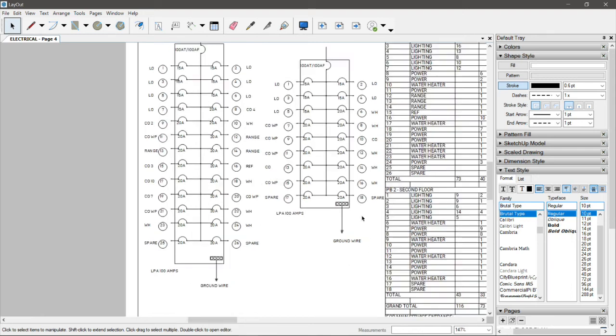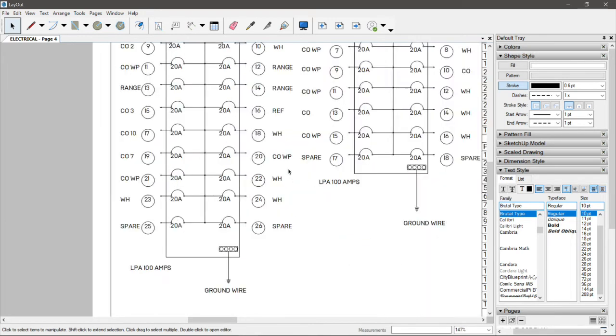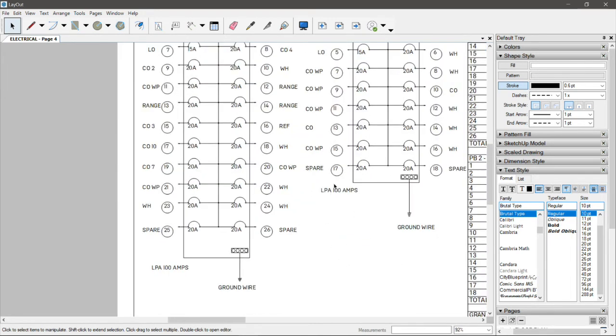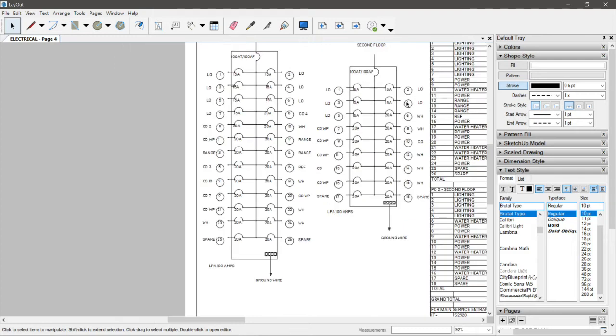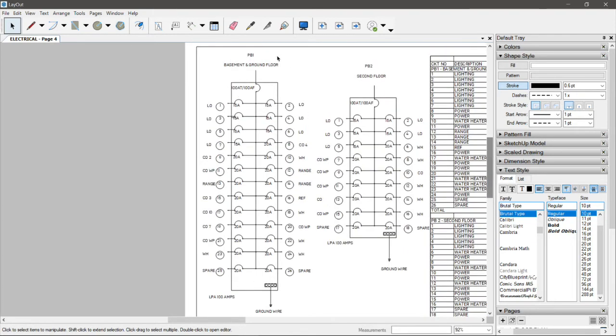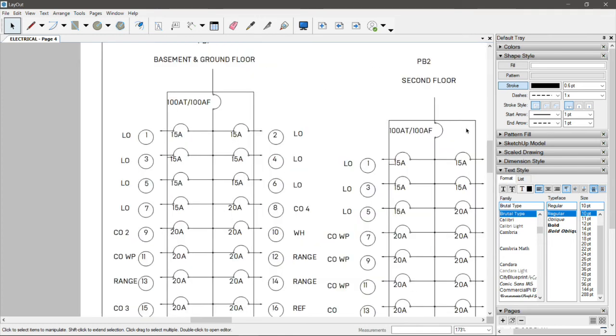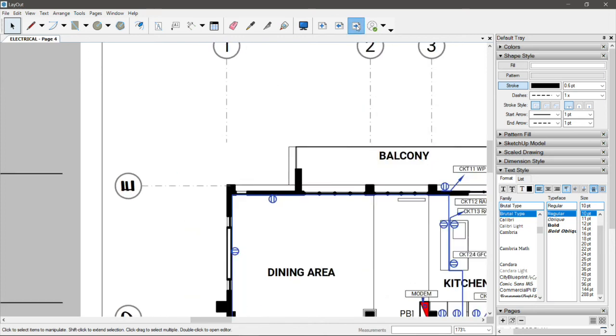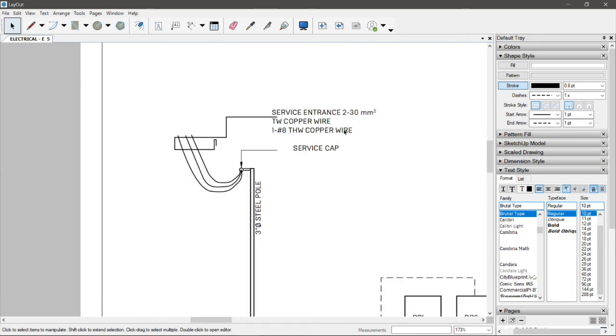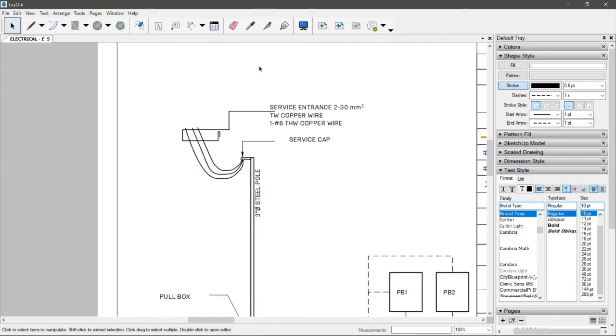And then have this checked by the professional electrical engineer. He is going to comment on your symbols, if they're actually correct, like a single pole or the labels of your PB1, PB2, the flooring, and if you could have this integrated or separated, if there are too much outlets in one circuit, or if the ATAF is correct and the same as in your service entry.